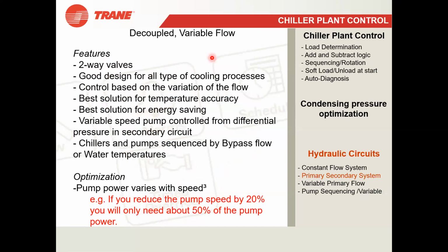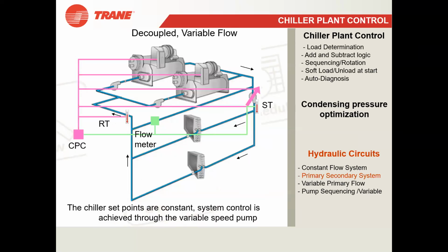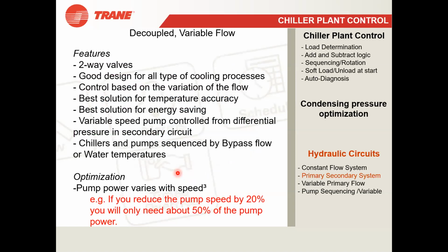So there will be two-way valves, and it is a good design for all types of cooling process. This decoupled variable flow uses primary and secondary both. This is a very stable design for all types of cooling process. And control is based on variation of the flow. You have understood how the controlling is happening. It is the best solution for temperature accuracy. If it is getting increased, you are throwing more through secondary. If it is getting decreased, you are throwing less through secondary. Okay. And at the same time, you are saving your energy also.